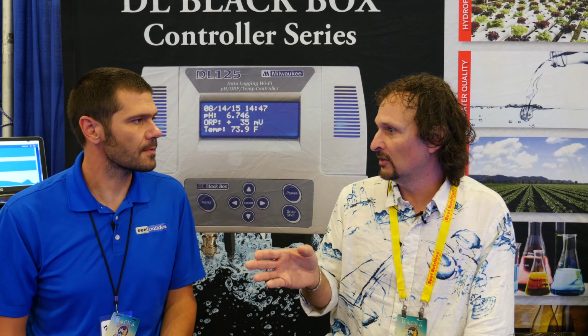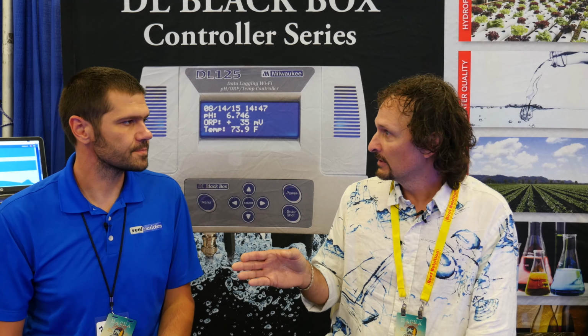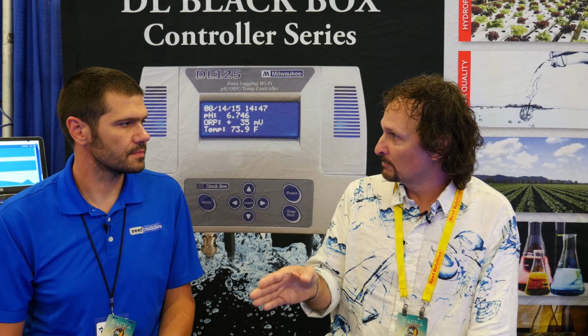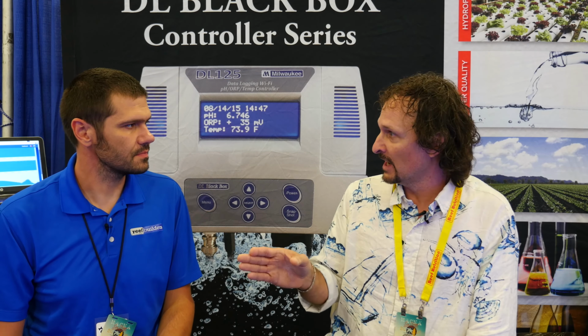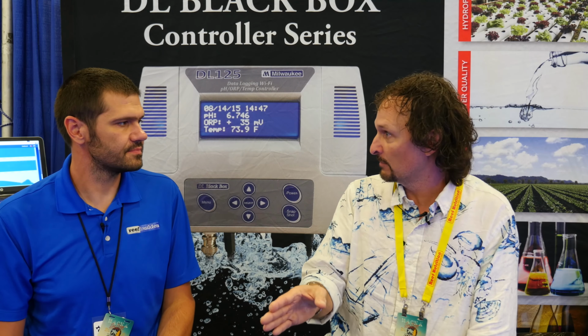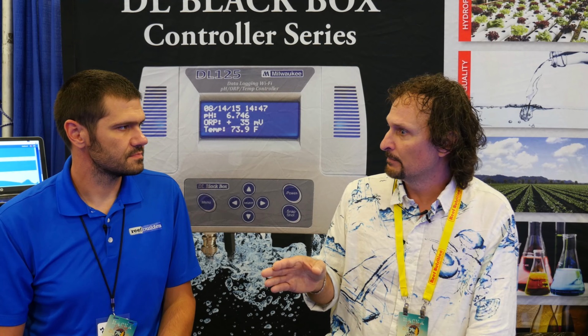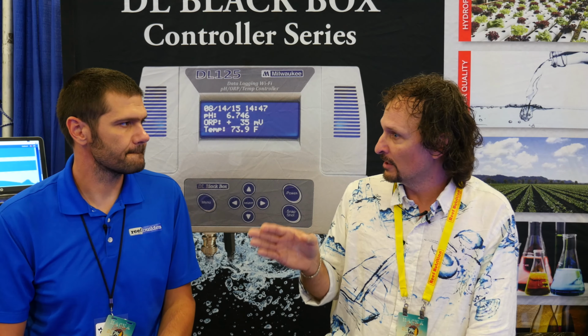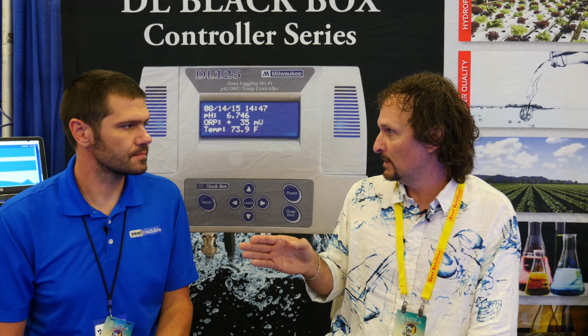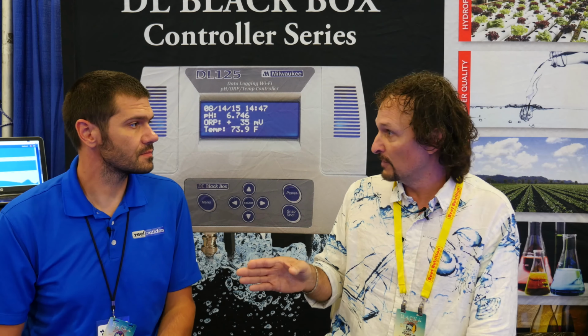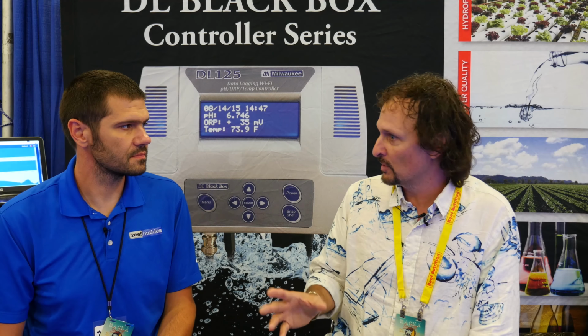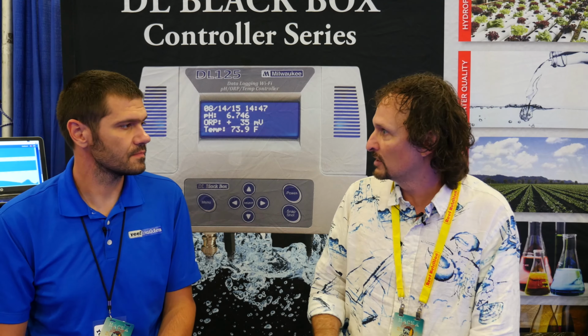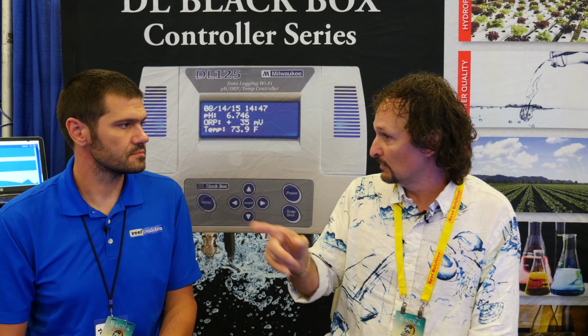Right. So what are some of the other features that really help your products give an accurate and precise pH measurement? Well, one of the other things is when you do a calibration, it also will do that probe diagnostic first and foremost, so you're not trying to calibrate to a bad probe or a probe that's going bad. We also have the ground loop preventer on both the pH and the ORP side, so any stray voltage is completely eliminated. You don't have to worry about trying to ground out the tank due to stray voltages and any of that stray voltage affecting your probes.